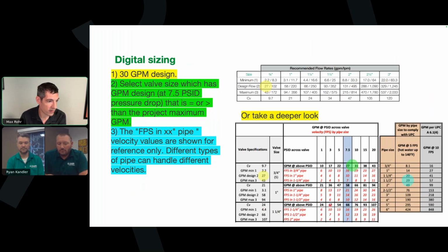But if we're going to 30 GPM and this valve comfortably will go up to 66, or even at a much higher pressure drop, 15, up to 93 GPM, we have a pretty, the analogy that we were using earlier was you have a pretty small steering wheel for a pretty big ship at that point, that you're going from 0 to 2% open back and forth versus the 3/4 inch valve, where you kind of have the whole swing there. So it's going to be more consistent because it's really fine tuning with a lot more to work with instead of just open, close at that lowest flow rate, which, if you hear the actuator moving a lot, could be another indication that you're oversized there. You shouldn't hear a digital mixing valve zzz, zzz, zzz, zzz, back and forth. That might be an indication of oversizing there.